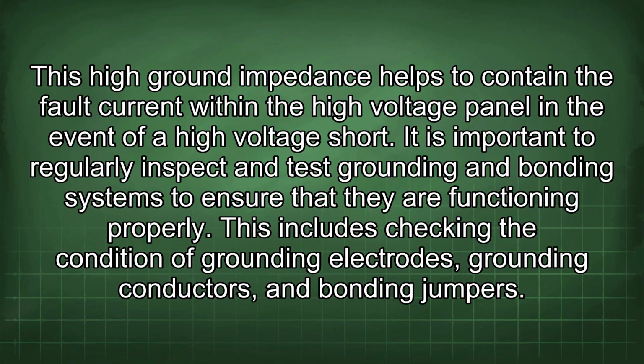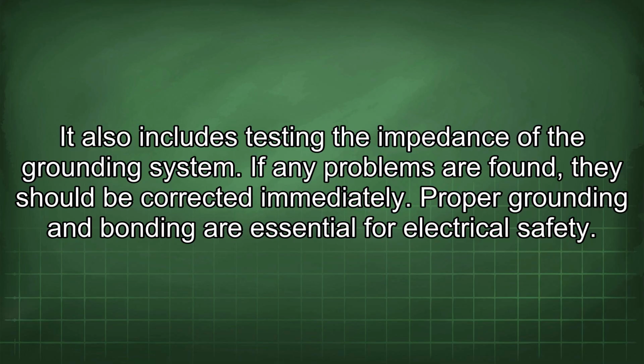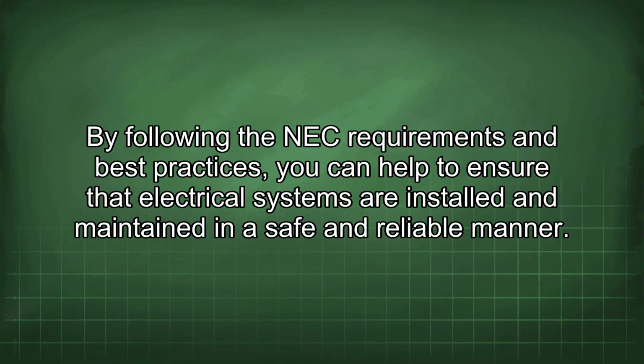It is important to regularly inspect and test grounding and bonding systems to ensure that they are functioning properly. This includes checking the condition of grounding electrodes, grounding conductors, and bonding jumpers. It also includes testing the impedance of the grounding system. If any problems are found, they should be corrected immediately. Proper grounding and bonding are essential for electrical safety. By following the NEC requirements and best practices, you can help to ensure that electrical systems are installed and maintained in a safe and reliable manner.